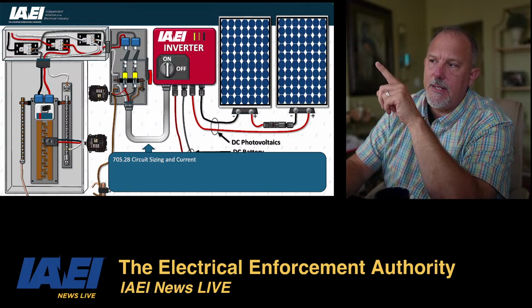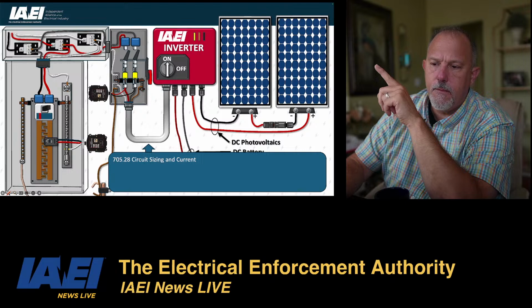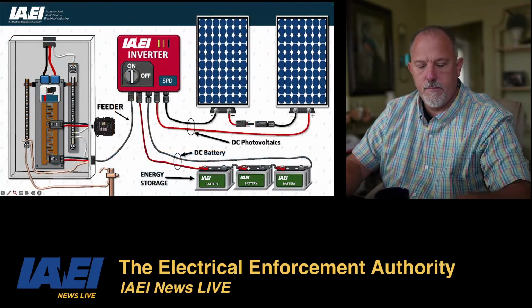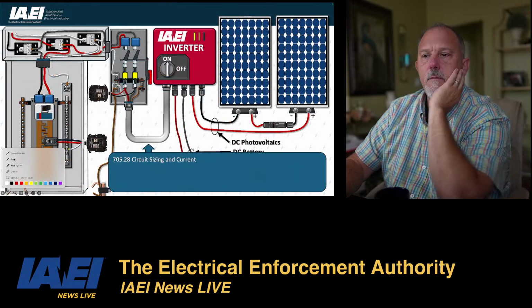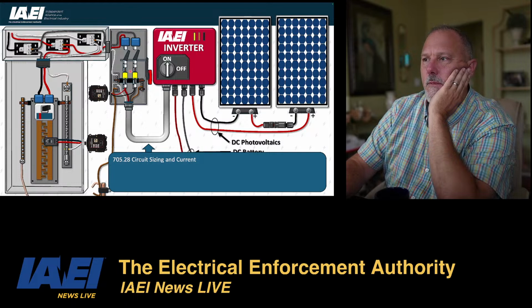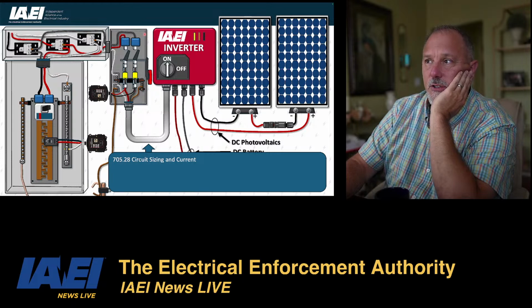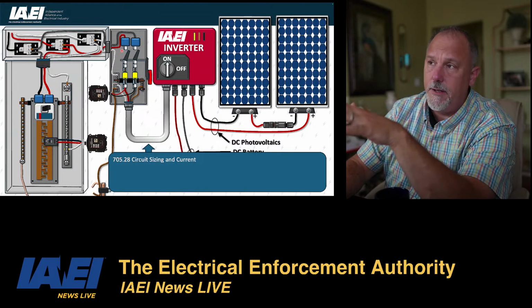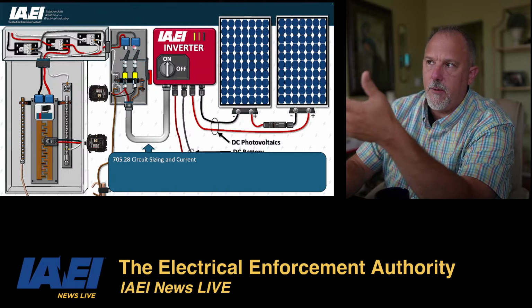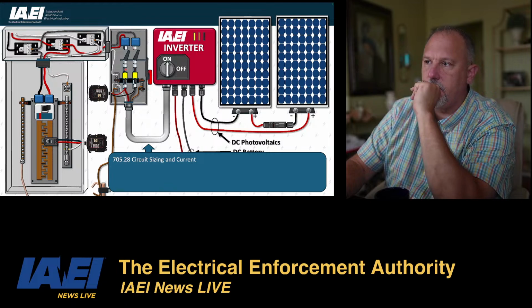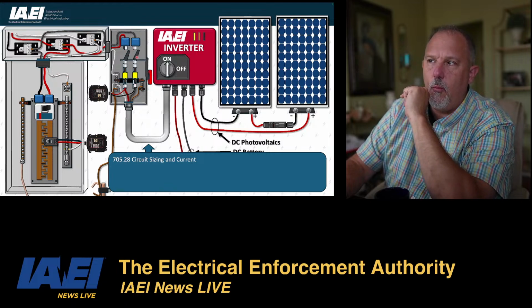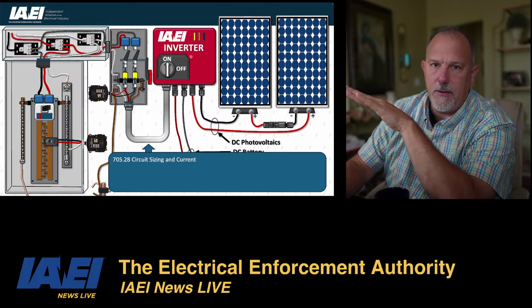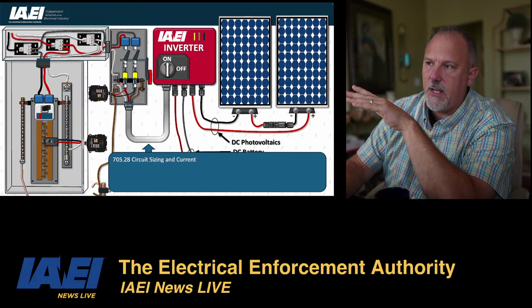If you look at these line side lugs, I should be able to get a pointer, shouldn't I? Laser pointer, there we go. I don't know if you can see this, but this set of lugs here, these lugs are barriered because they're coming from the utility, they're always on. If I open this disconnect switch, I want to make sure that I barrier off those energized parts. The moment I open this disconnect switch, this inverter shuts down, so I don't have these terminals energized.